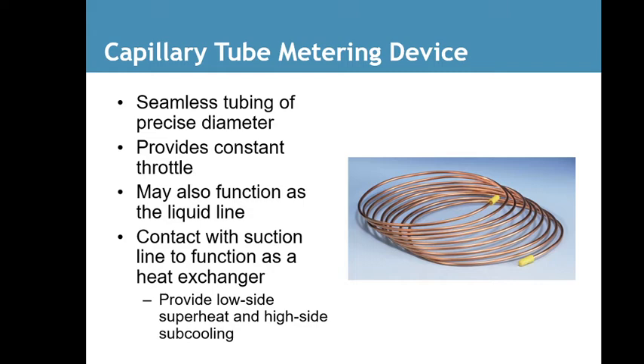They also may have functions in the liquid line, conducting contact with the suction line to function as a heat exchanger. A lot of metering devices, for example, you'd have a capillary tube in most refrigerators running around the inside frame of the door, not the actual door that swings open and closed, but the box that the door closes on. It runs around that. So you're always pumping high temperature refrigerant around that door, and you're saying, why do they do that?